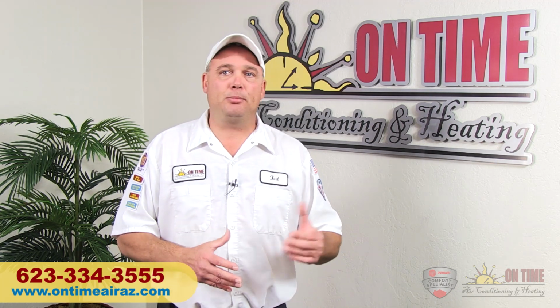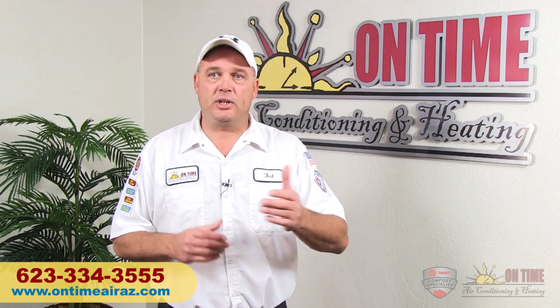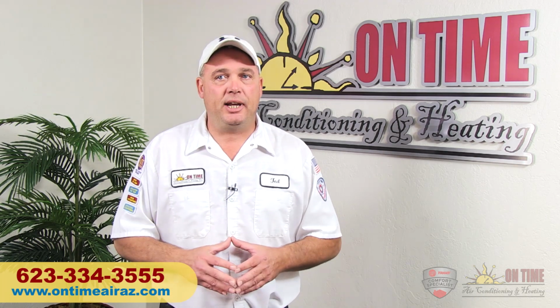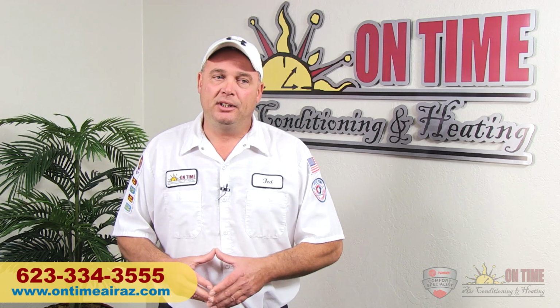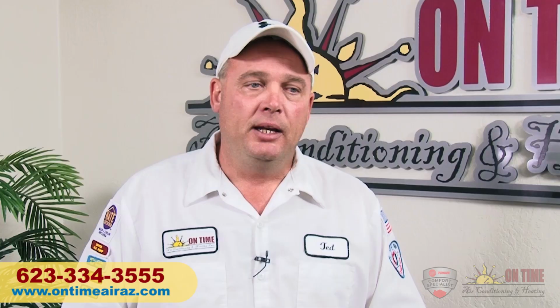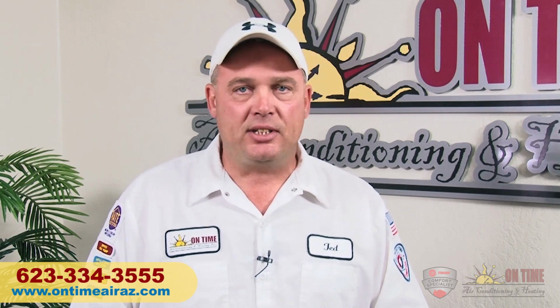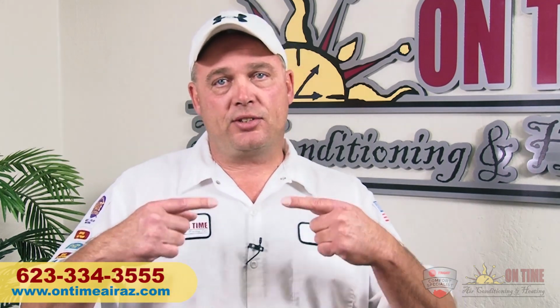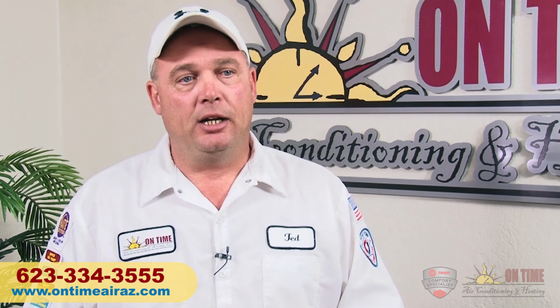The difference between a standard blower system and a variable speed blower system is we can actually set switch settings to tell that motor how to operate. Most of your units today pretty much come on 100%, they shut down 100%, so you either get a blast of hot or cold air in your home when the unit first turns on. These systems here, we set them up for what we call Comfort R settings. And basically what happens is the unit comes on for cooling or heating. That motor slowly starts to turn. It takes about 5 to 6 minutes to reach 100% of airspeed.